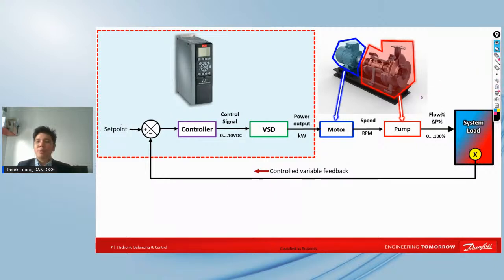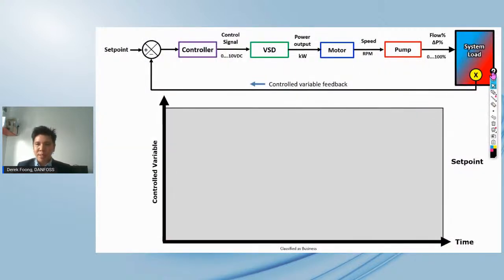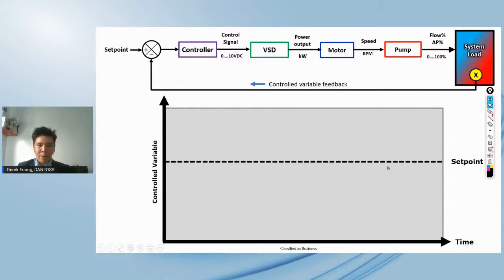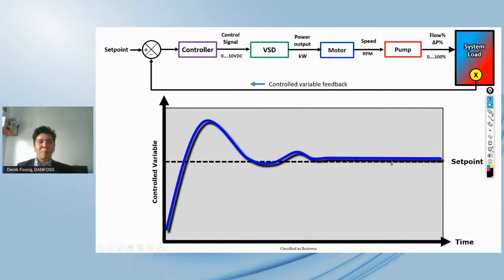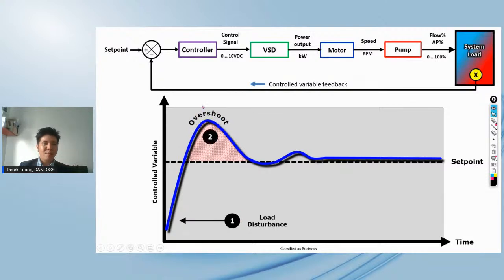All right, so now let's look at a bit of the control behavior. When you look at the control behavior, let's say, for instance, you have the set point, and you start up a pump. This is normally what we see: if we start up the pump, the pump will start to ramp up and build the pressure up in the system. Then you would have a little bit of overshoot here when we look at the anatomy of this behavior. We always call this either load starting or load disturbance. Then when it comes up here, we call it overshoot.